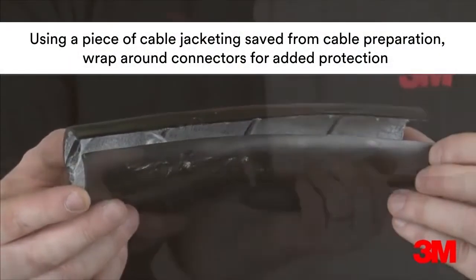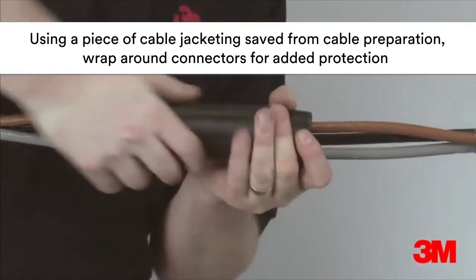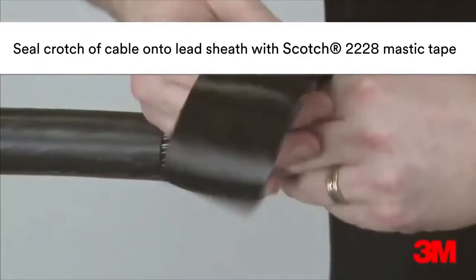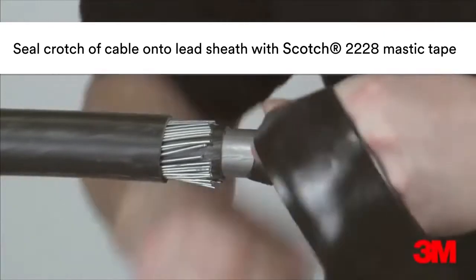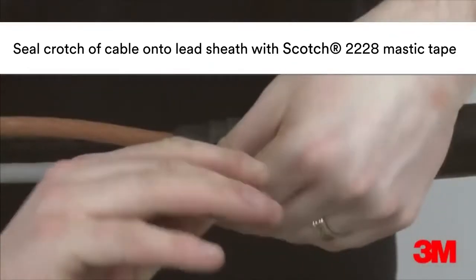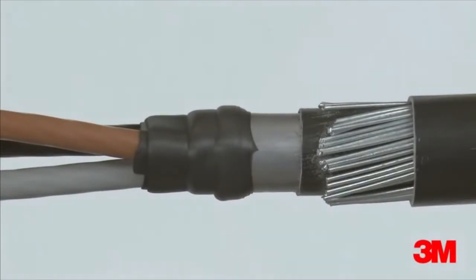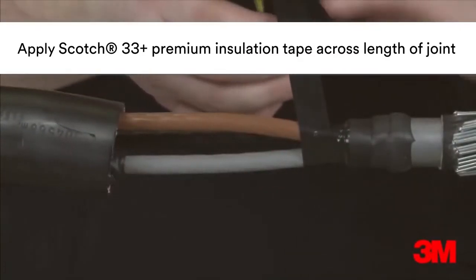A piece of cable jacketing that has been saved from the cable preparation is then wrapped around the connectors for added mechanical protection. Scotch 2228 mastic tape is then used to seal the crotch of the cable. Scotch 33 plus premium insulation tape is applied across the length of the joint.